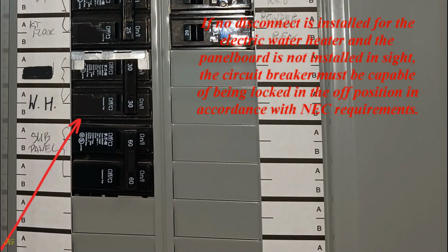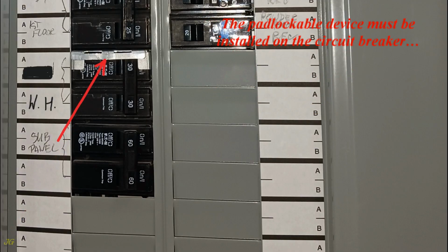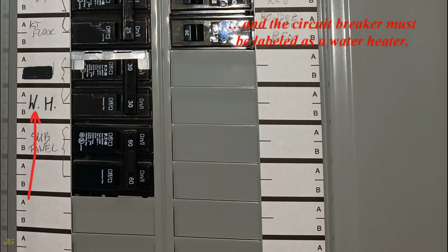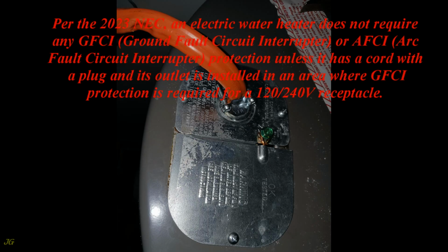If no disconnect is installed for the electric water heater and the panel board is not installed in sight, the circuit breaker must be capable of being locked in the off position in accordance with NEC requirements. The padlockable device must be installed on the circuit breaker, and the circuit breaker must be labeled as a water heater. Per the 2023 NEC, an electric water heater does not require any GFCI, ground fault circuit interrupter, or AFCI, arc fault circuit interrupter, protection, unless it has a cord with a plug and its outlet is installed in an area where GFCI protection is required for a 120-240 volt receptacle.